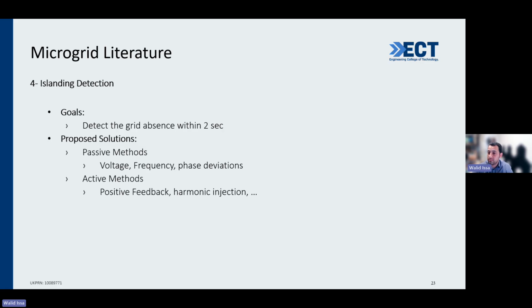And for islanding, now I think some of you may be aware of what we mean by islanding detection. For example, if you have an inverter in your house and you have solar power, you send that power to the grid. But what if the grid is absent? What if the grid has a problem and they disconnected that breaker, or the transformer between you and the grid has been blown up, or the fuses have been blown? What will happen to your inverter? Will it keep supplying that power to the transmission line, making a risk for any maintenance worker who wants to work on that line, or will it cease the power and stop? This is called islanding detection.